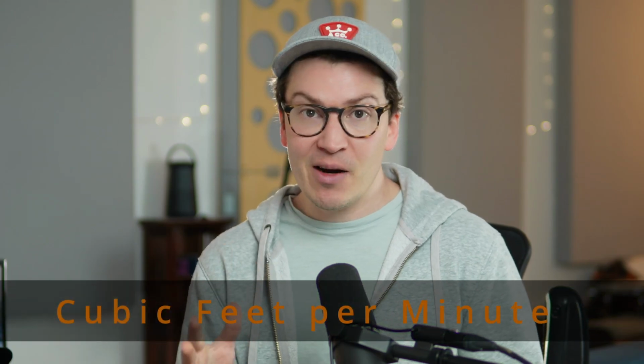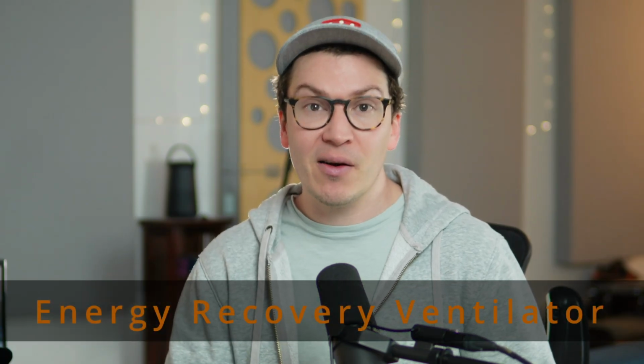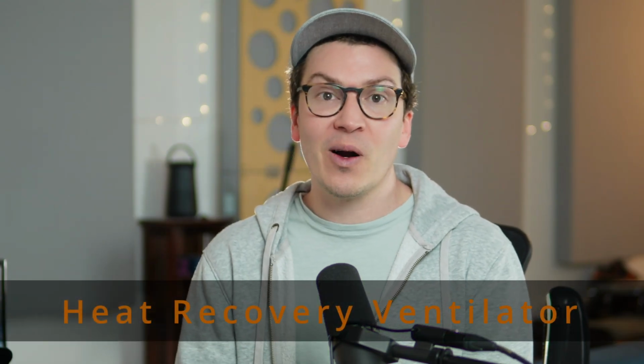If you are going to be using an ERV system, then you're going to have the CFM, meaning the cubic feet per minute of airflow that is going to be coming from your ERV, which stands for Energy Recovery Ventilator. You may be using an HRV, meaning a heat recovery ventilator, if you are in a certain climate like the Southwest where it's dry and hot, or very, very cold. So dry places technically use an HRV, and moist, more humid climates tend to use an ERV. In the United States, ERVs are generally what we're going to use for most climate zones. So let's say you have 150 CFM coming into your baffle box. Well, that's fairly easy. Now we know we have 150 CFM, so we're going to design the baffle box for that.